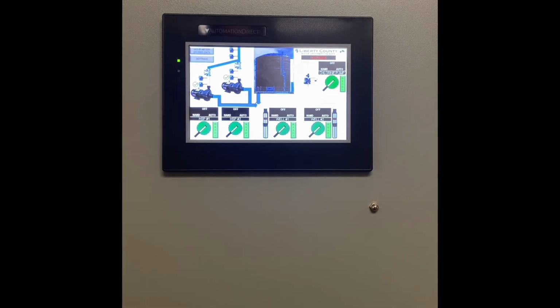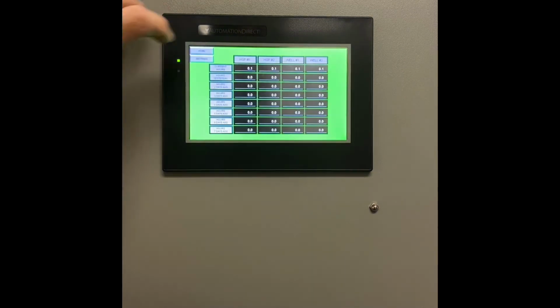So we'll start in the upper left, and we have 2 push buttons. One says hour meter stored data, and the other one says settings. So we'll touch the hour meter stored data. That brings us up to a screen. The top row across, left to right, is the current hours for each of the pumps. Moving down from there is 1 day previous, adding each day down until you get to 7 days previous to today. Those numbers will move at midnight every night without fail.